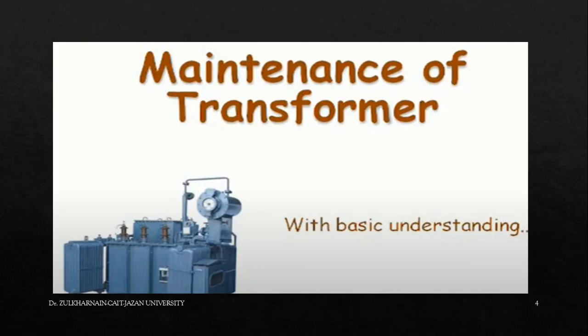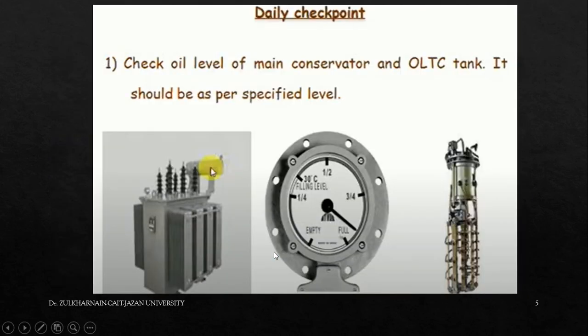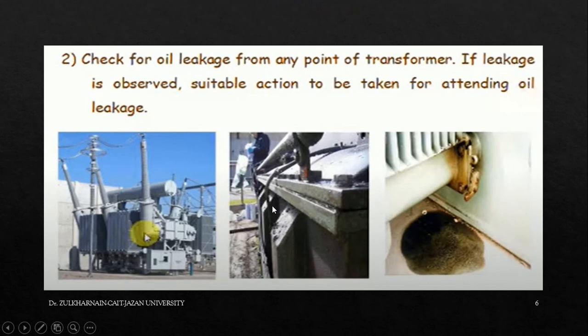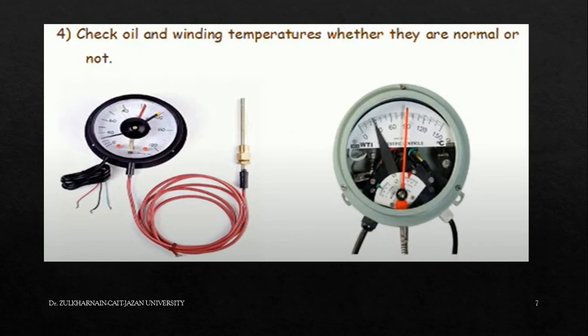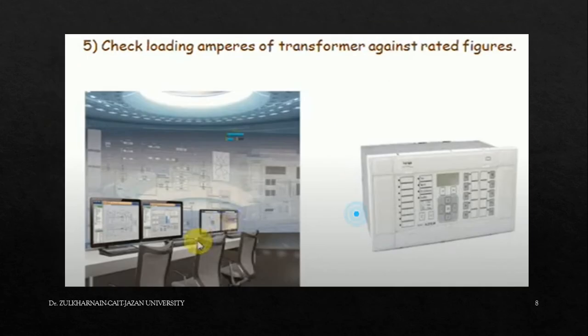Now you need to know what all the things that you need to have for maintenance of a transformer. First of all, a very important thing is the checking of oil level, because oil keeps on leaking and there is every chance that oil may dry up, and thereby the cooling system on the transformer may become problematic. So you have to check oil and check for the temperature of the winding and see that they are replaced and maintained.